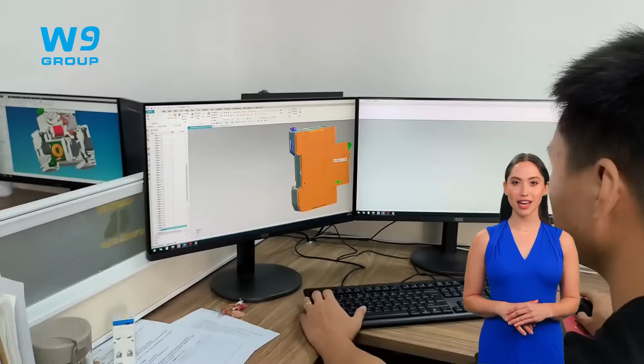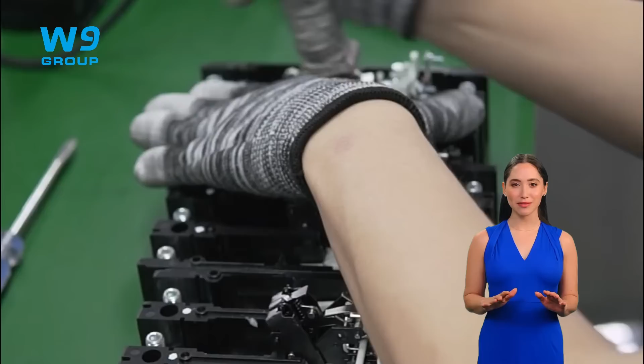In W9 Factory, we have a GPL3 high and low temperature alternating humidity and heat tester with temperature settings of 40 degrees C and 70 degrees C, which can independently check the mechanical life of the circuit breakers, short circuit, short delay time, overload, long delay time, as well as test product parts for flame retardance, compression resistance, copper plating, and so on to meet the customer's quality requirements at the factory.